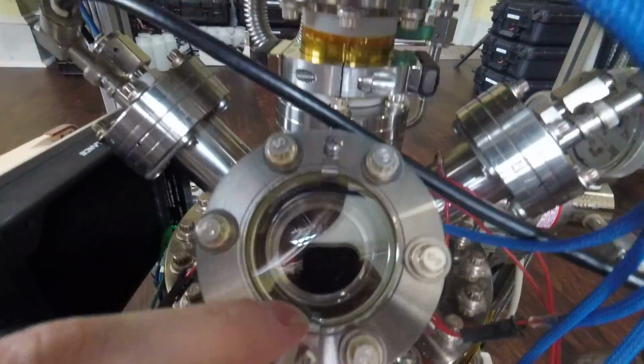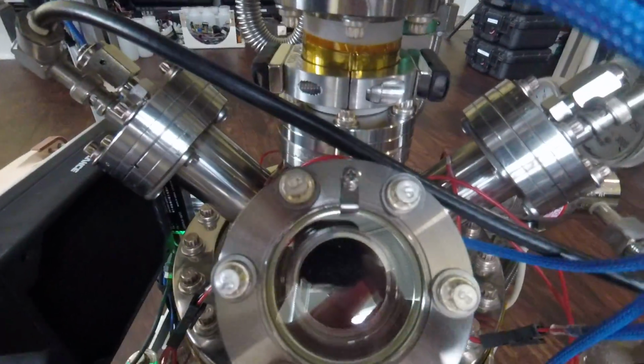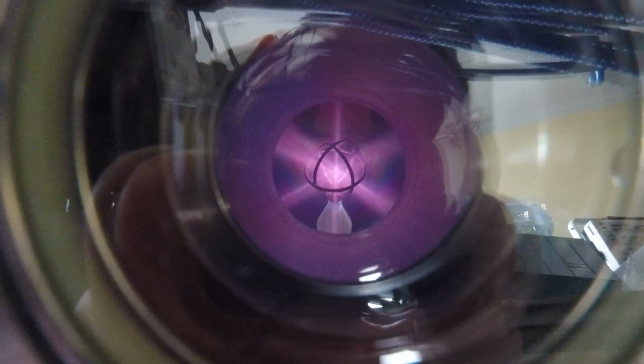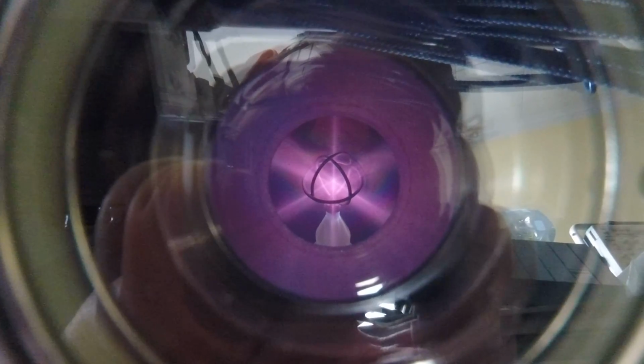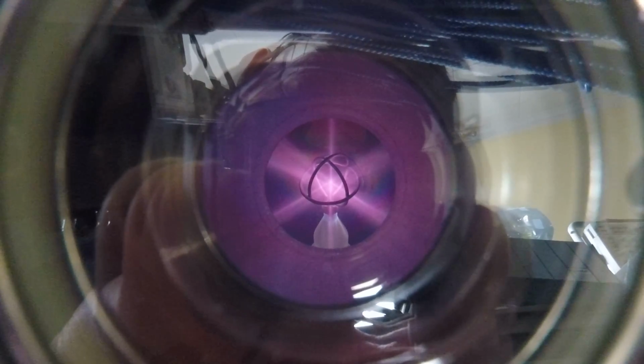So, giving a close-up of the plasma, I'm going to bring this onto the viewport, and this viewport does have a lead glass shield for X-ray safety. And turning on, you can see the plasma form, and you can see that the ion beams coming from the upper and lower left and right are considerably higher in density. This is because that's where the four ion guns are located. Those are the anode layer ion sources.